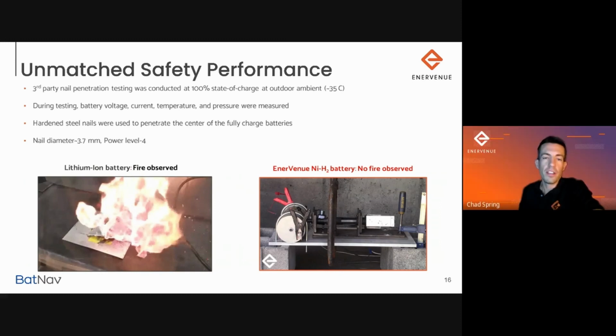If you think about NFPA guidelines, NFPA 855, in the event of a hydrogen leak or dissipation, the requirement is that it needs to be immediately vented with ambient air and released to atmosphere. Hence our systems we showed earlier, our 20-foot containers, have hydrogen detection and ventilation to comply with the NFPA requirements. Additionally, lithium batteries also outgas hydrogen in a thermal runaway event, so we're not doing anything new or different here in our safety precautions.